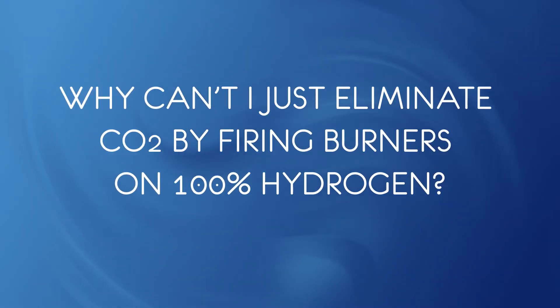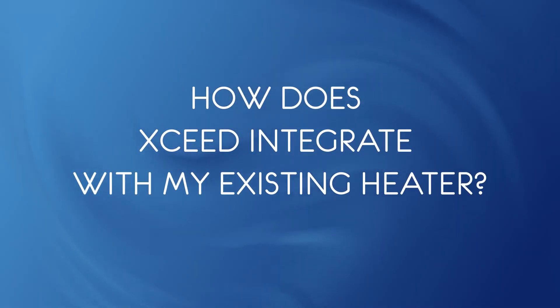Why can't I just eliminate CO2 by firing burners on 100% hydrogen? The heat flux profile on most fired heaters does not allow this without overheating the tubes. 100% hydrogen operation increases the radiant section and heat transfer, but it does so unevenly. Existing hot spots will likely become worse. The Xceed system also allows for increased throughput while reducing CO2, something that's typically not an option with traditional burners alone.